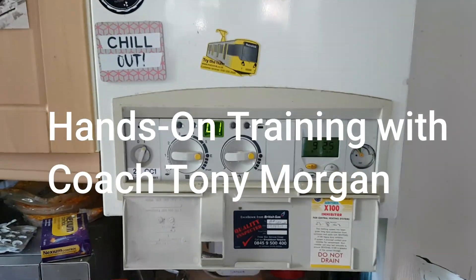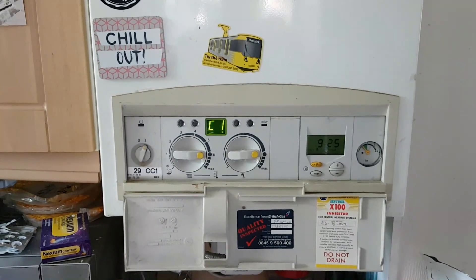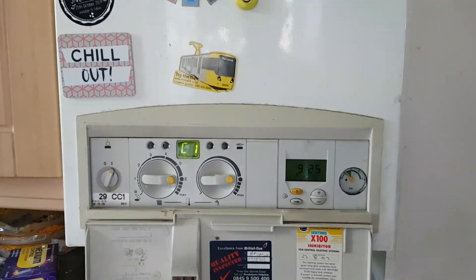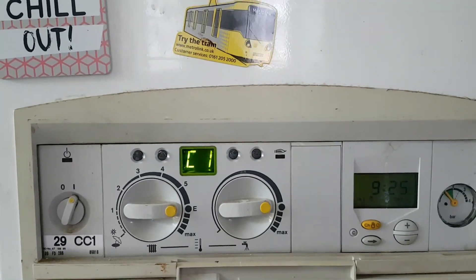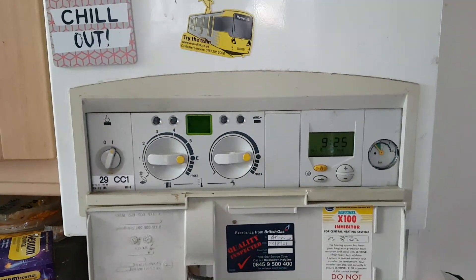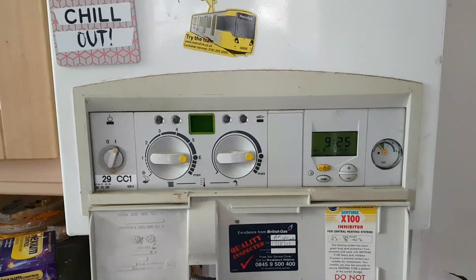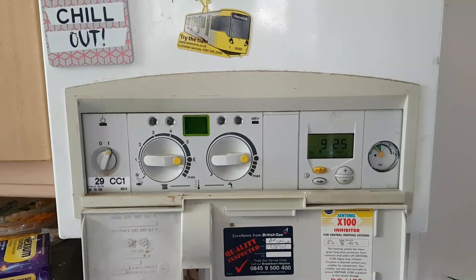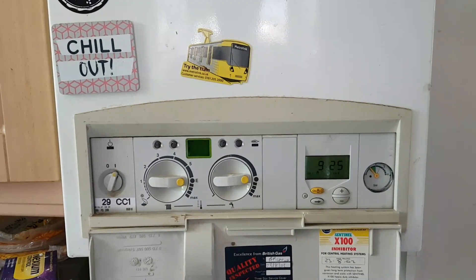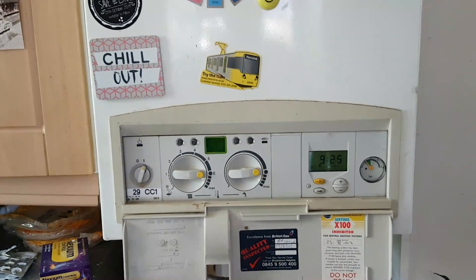Hi, this is Coach Tony Morgan and today's video is on a British Gas 29 CC1. The fault on the boiler you can see is a C1 flashing — that means the fan unit is not working. When you turn the boiler on you can hear the fan racing away, that's the first thing you normally hear. Apart from the pump running, on this boiler it's quiet, so we're going to go inside the boiler and diagnose the fan.